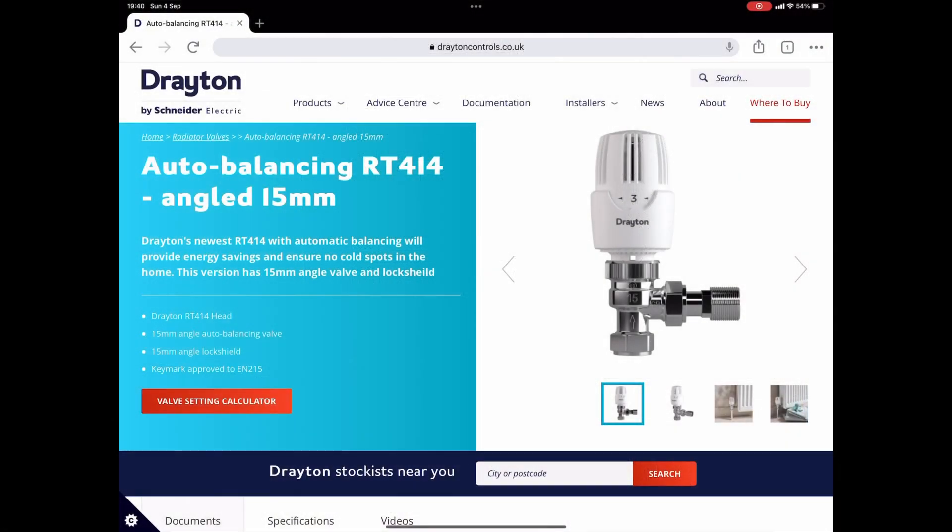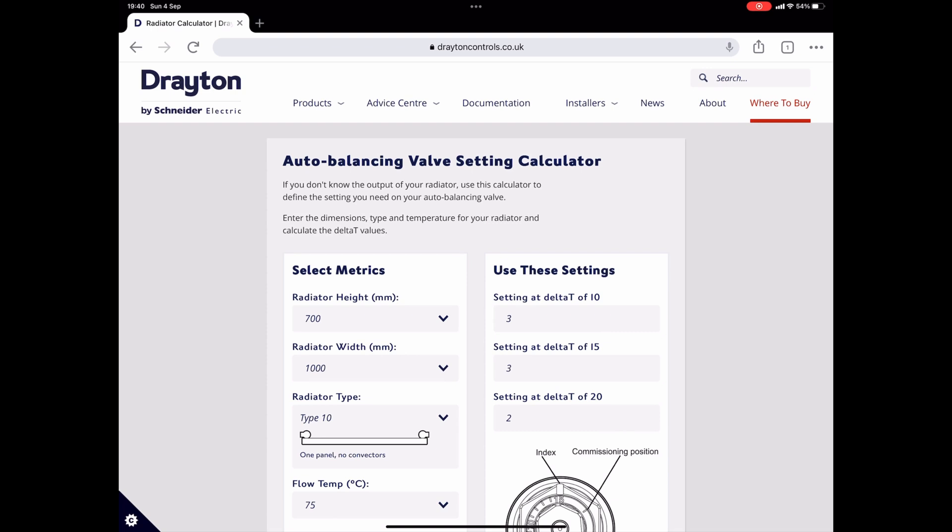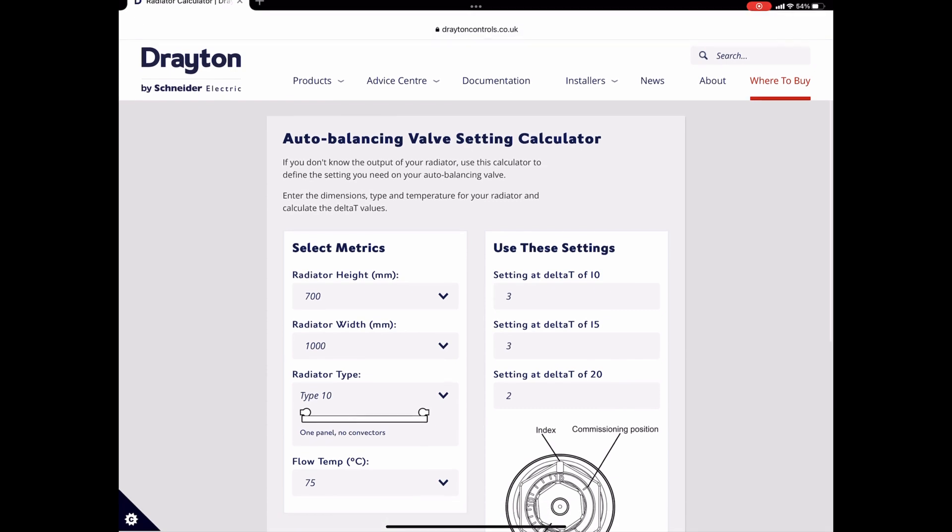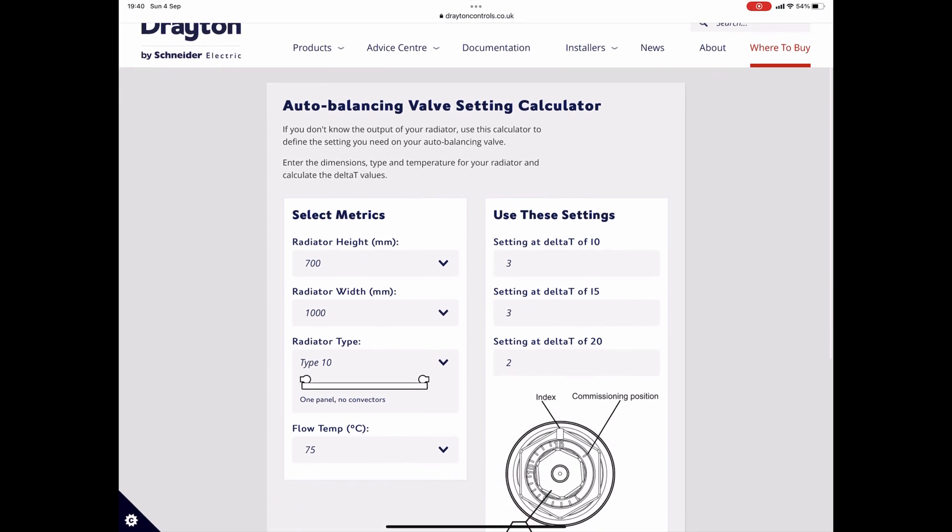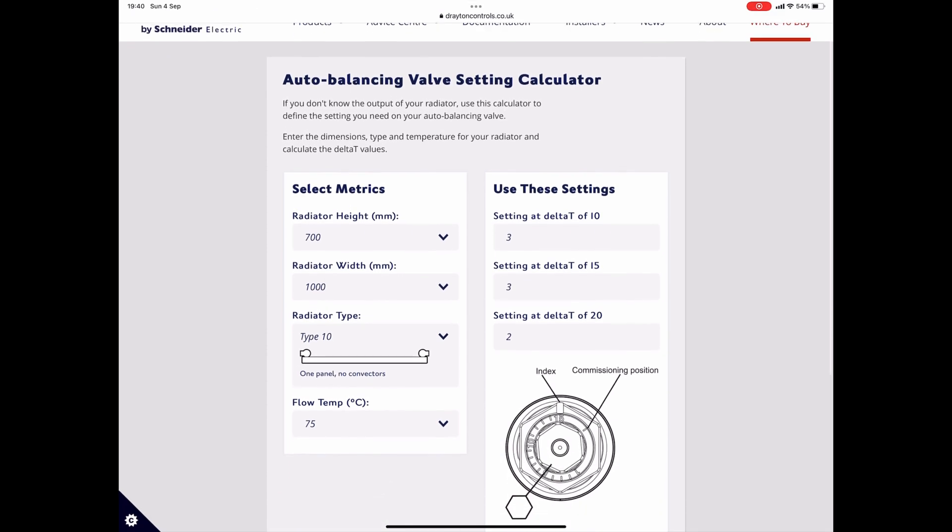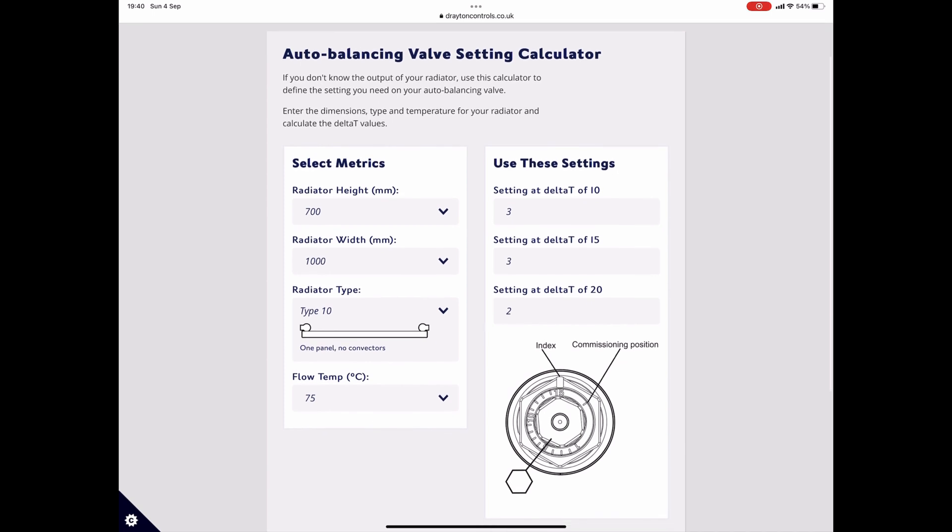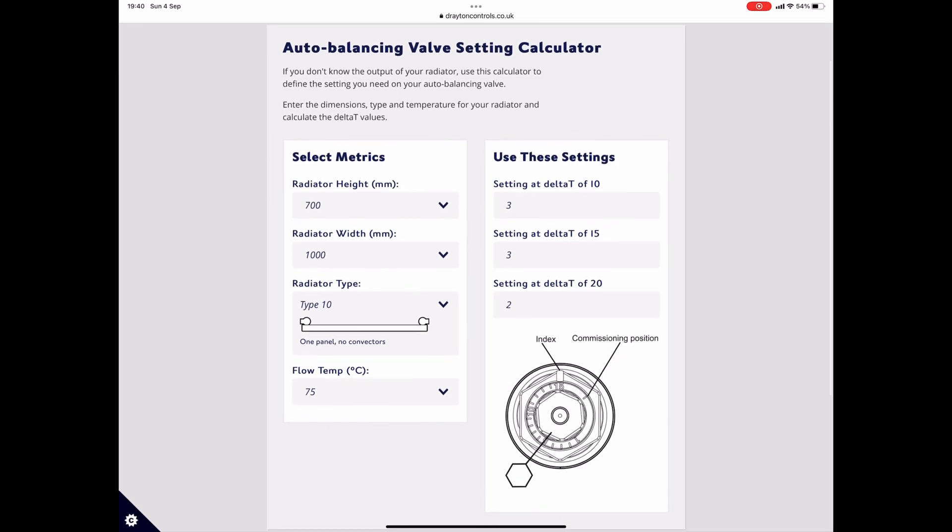The second method is used where you don't know the output of the radiator. Head over to our website and there is a valve setting calculator whereby you put in the radiator size, the type of radiator, your desired flow temperature and that will again give you three settings based on three differential temperatures.